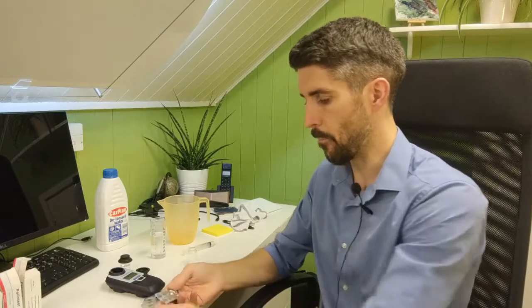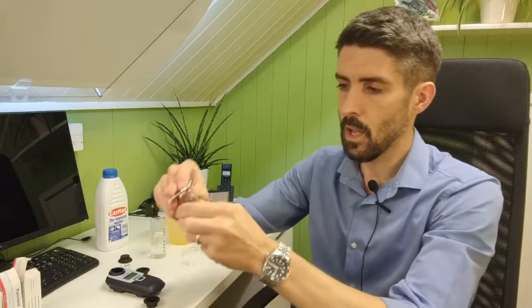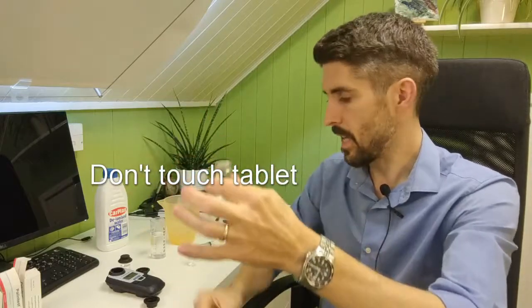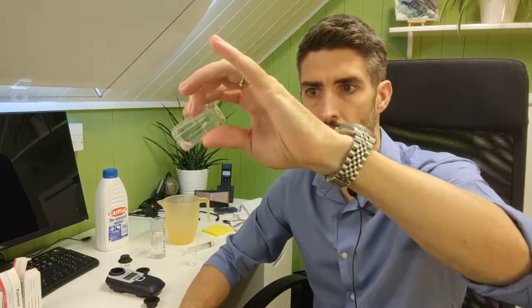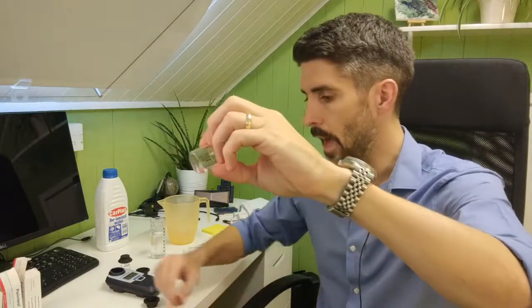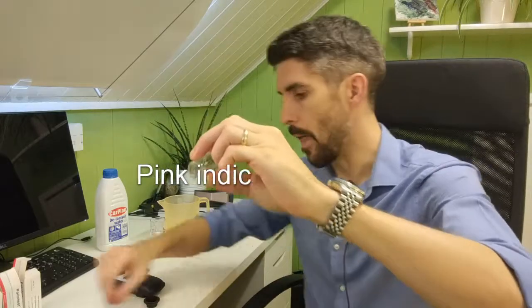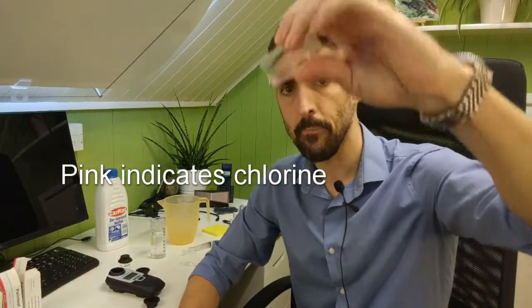So a DPD1, what you do, a little bit of water, tablet goes in without touching the tablet with your fingers. You don't want to touch the tablet with your fingers or else you're going to affect the result. And you'll see it go pink. That tells us that there's chlorine in there. There's definitely chlorine in there, or else it wouldn't go pink.